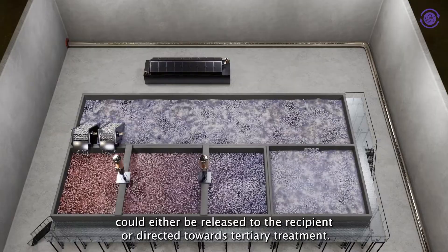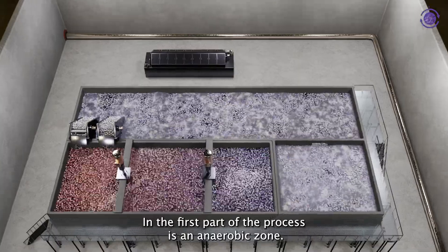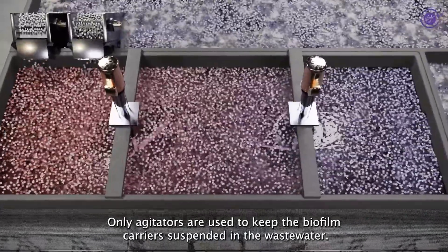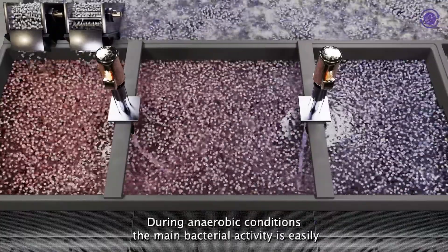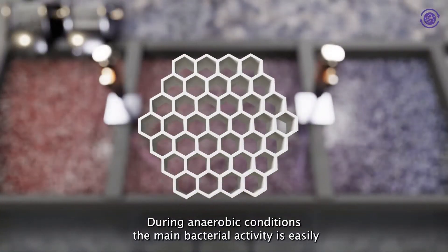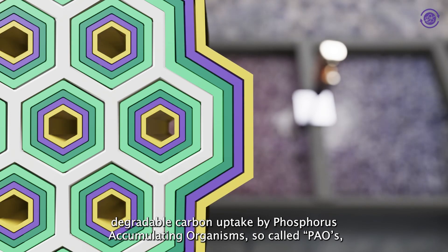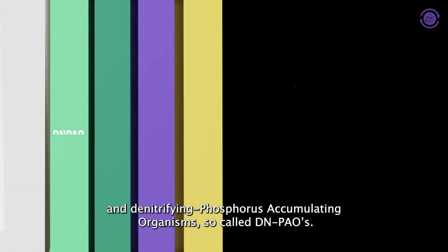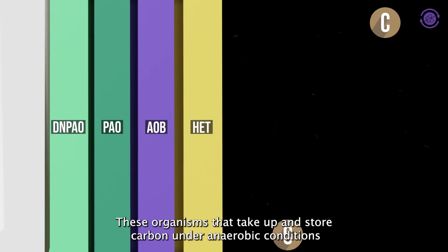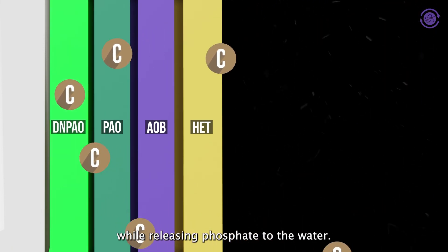In the first part of the process is an anaerobic zone. Only agitators are used to keep the biofilm carriers suspended in the wastewater. During anaerobic conditions, the main bacterial activity is easily degradable carbon uptake by phosphorus accumulating organisms, called PAOs, and denitrifying phosphorus accumulating organisms, called DNPAOs. These organisms that take up and store carbon under anaerobic conditions are releasing phosphate to the water.